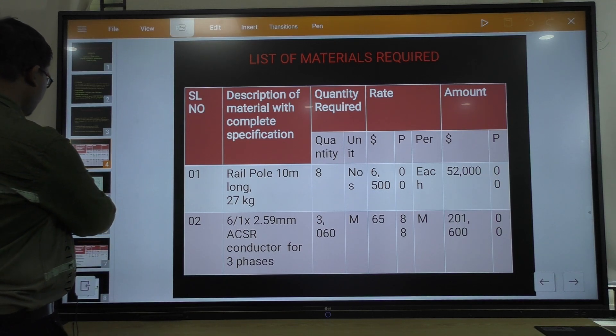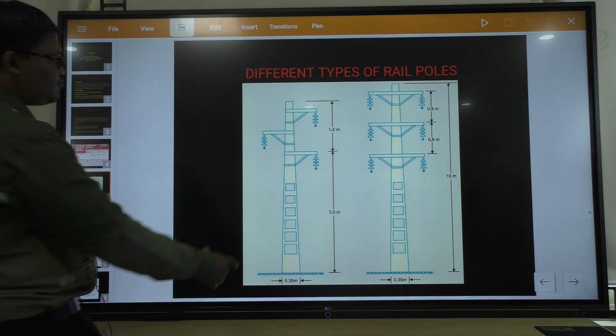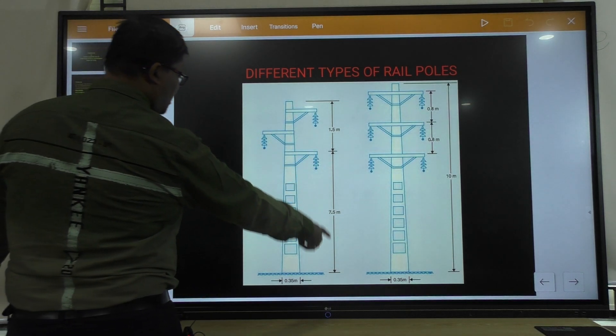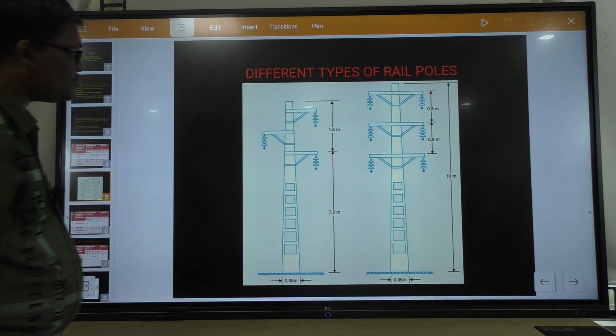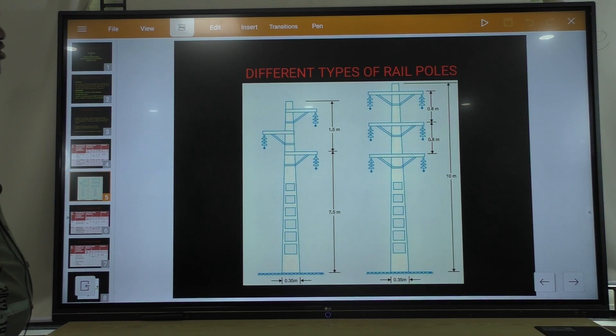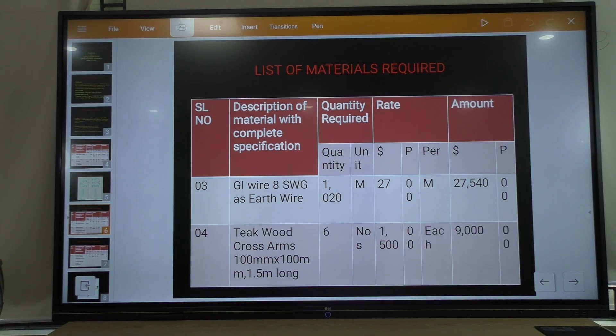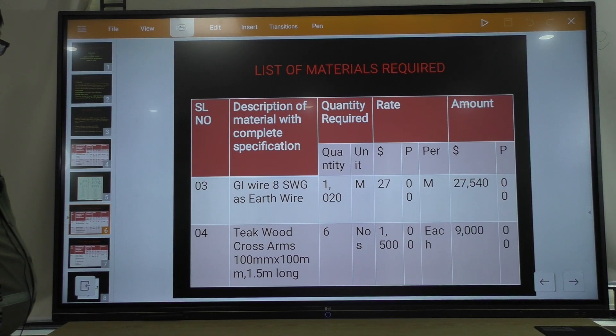Next, the different types of rail poles require cross arms. The minimum distance from one cross arm to another is 1.5 meter, and from the bottom cross arm to the ground floor is around 7.5 meter. For L-type cross arm and T-type cross arm, the distance between two consecutive cross arms is 0.8 meter and total height is around 10 meter. GI earth wire 8 SWG, 1020 meters is required.